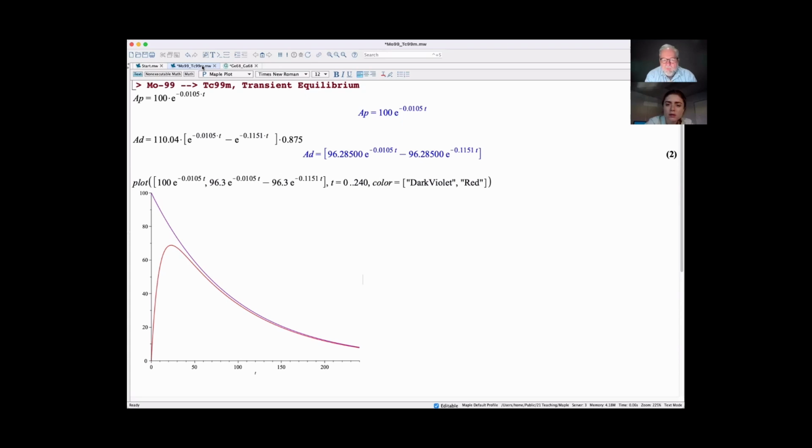So you're going to have some impurities. In the case of either moly-99 or germanium, some of that's going to get washed out, and we check this. That's called breakthrough. So we check to ensure that the breakthrough is at an acceptable level. But the other thing that happens is that elution is not 100%. It doesn't pull off all of the technetium or all of the gallium-68 during the elution process. So we talk about yield. This is where the chemistry comes in.